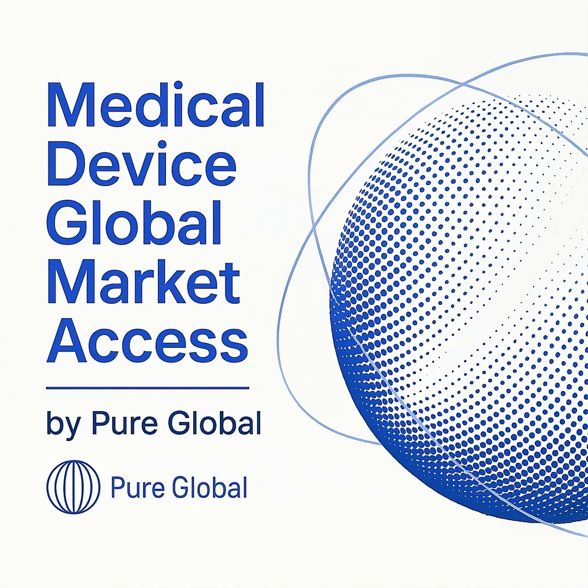Manufacturers often struggle with unclear distributor or importer roles, sometimes vaguely called customers or partners, despite clear IVDR definitions. This applies even to software or complex international supply chains involving non-EU countries like the UK and Switzerland. Another common issue is quality agreements not clearly defining or referencing IVDR obligations, offering no proof of compliance. While economic operators like distributors don't need an ISO 13485 QMS, the legal manufacturer must verify their qualification and IVDR compliance. Older agreements need updating.